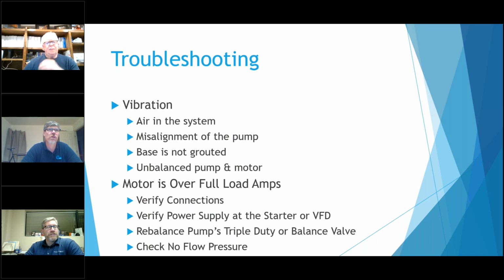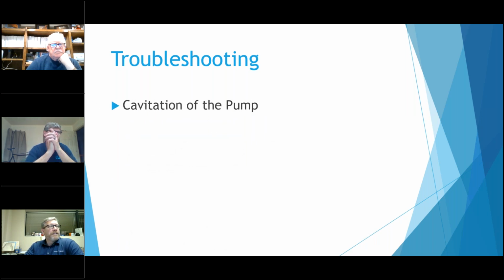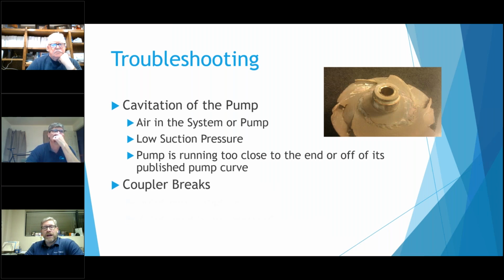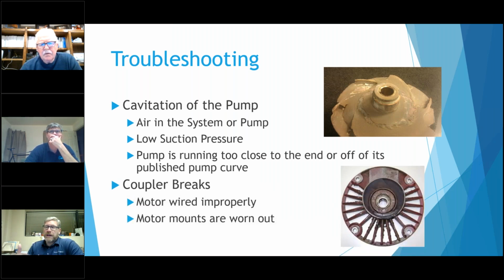This is just kind of troubleshooting vibration and the full amperage. You're over amping. Here's a nice little picture of a cavitated impeller, where you can get some air in the system or low suction pressure. Another common thing we see is coupler breaking.